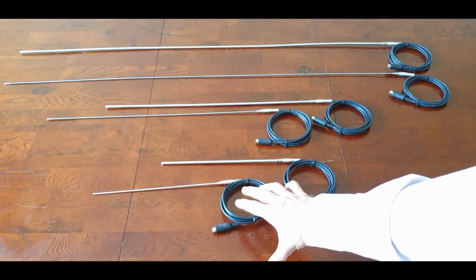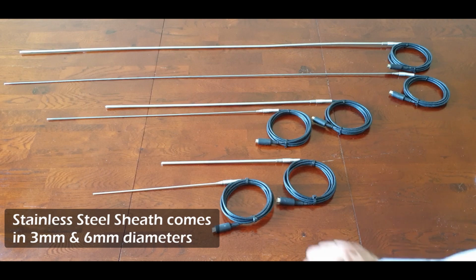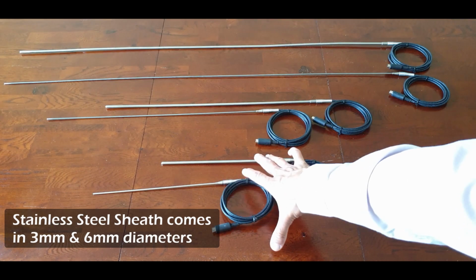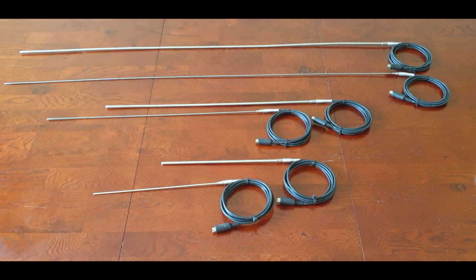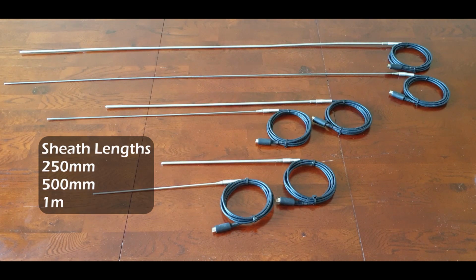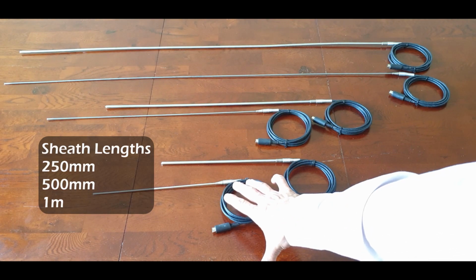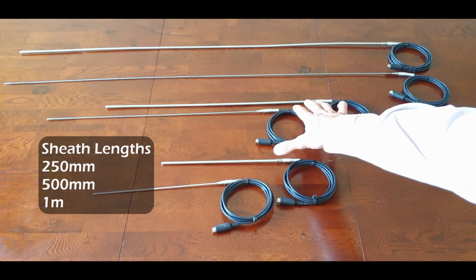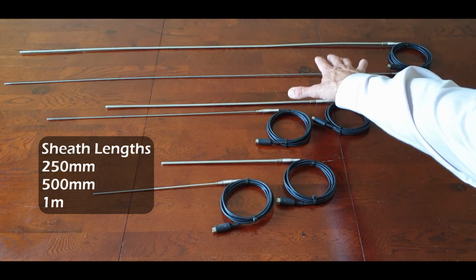In this video I'll be taking you through our high and low temperature mineral insulated PT100 Class A 4-wire temperature probes. The probe sheath is made out of stainless steel and it comes in two different diameters, a 3mm diameter and a 6mm diameter. They come in three different lengths: 250mm, 500mm and 1 meter.